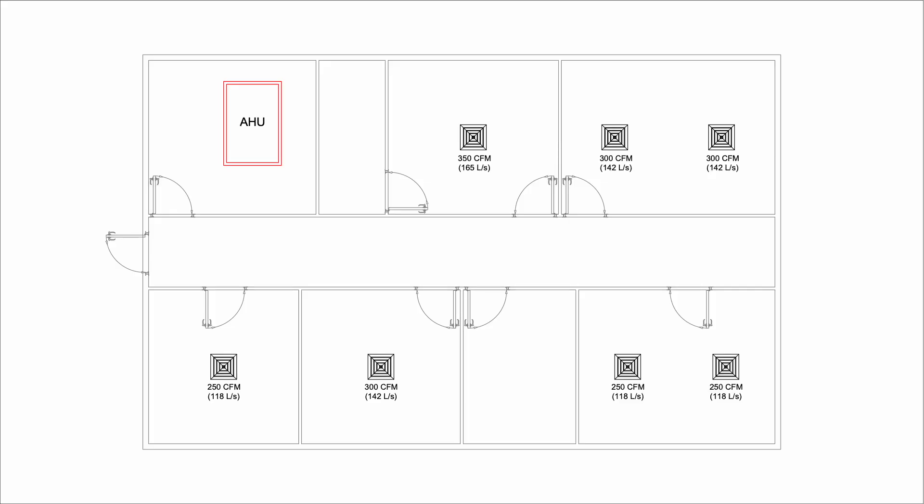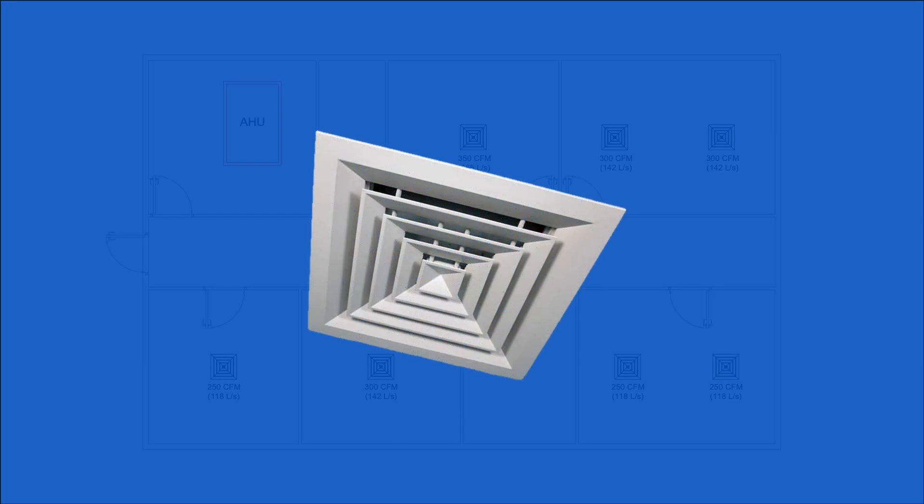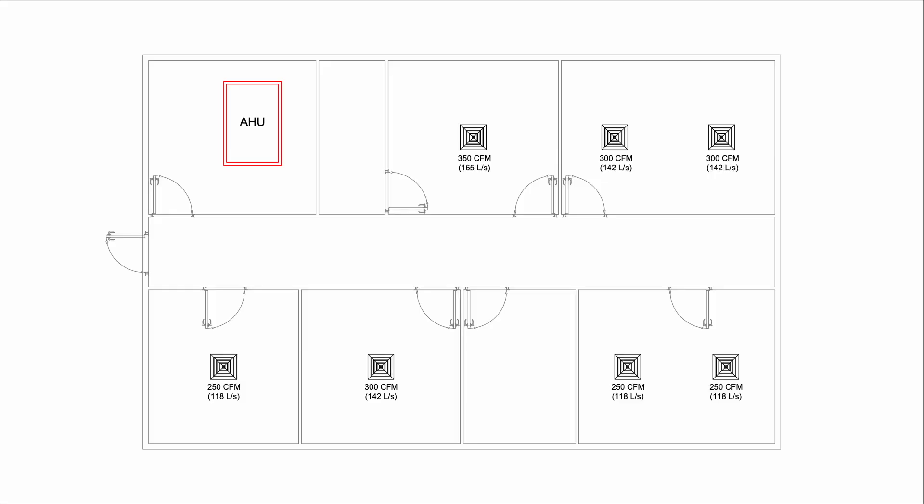We start by selecting the supply air diffuser type. Here, I use 4-way ceiling diffuser. For this type of diffuser, we generally want to aim for about 250 to 350 CFM per diffuser. That will decide how many diffusers we need.